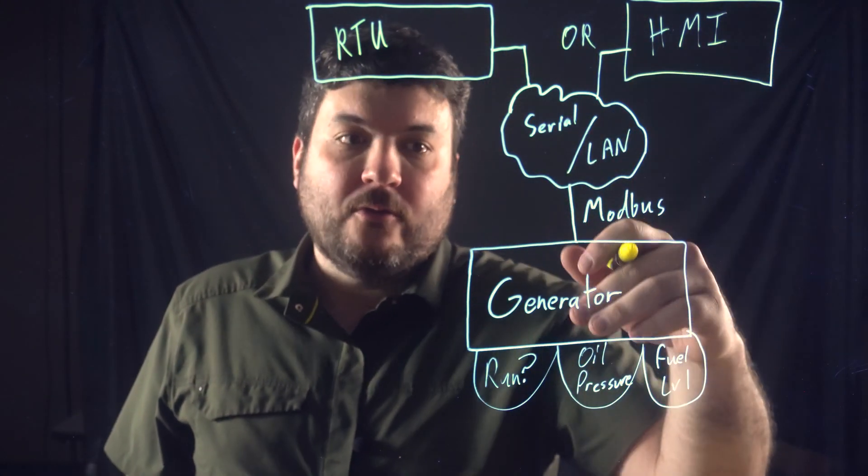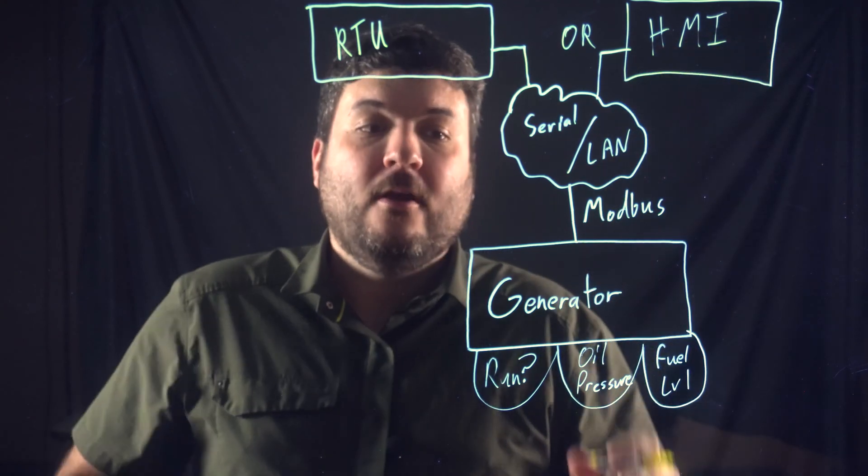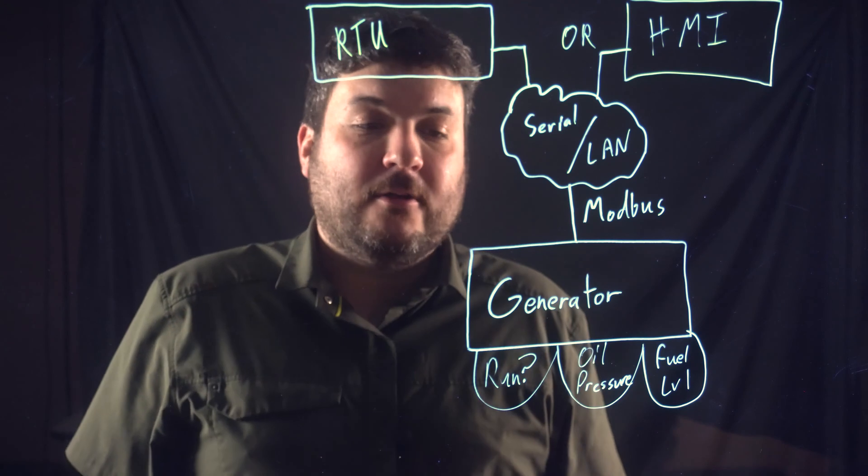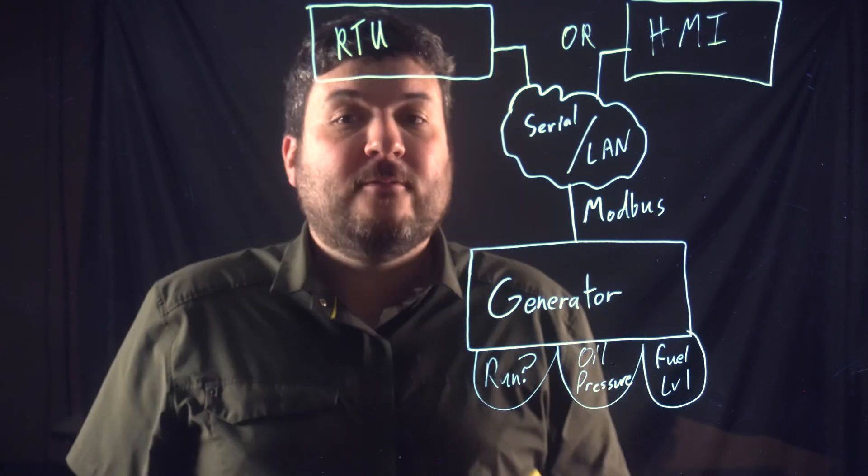So what happens is these devices are capable of sending Modbus polls. They're going to ask the device on a regular basis, what's going on? And then it will reply back, well, I'm currently running or I'm not currently running. This is my oil pressure. This is my fuel level.